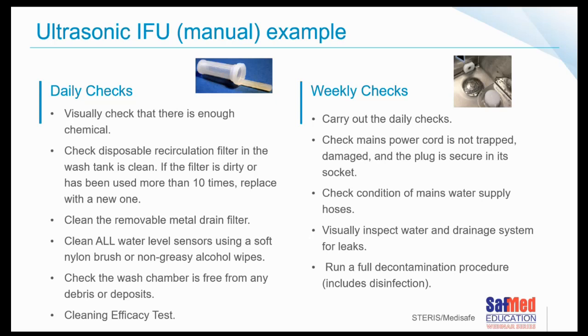A lot of them have got water level sensors, so that's how it knows how much to fill. Of course, it fills up a set amount and doesn't overflow. There's some form of sensor to measure that, and you may need to clean those using a nylon brush or an alcohol wipe, whatever the instructions say. Check that the chamber itself is free from any debris or deposits. You may need to be doing, and you should be doing, cleaning efficacy tests. How often are you doing them? How are you doing them? And then there may be weekly checks, in addition to your daily checks: checking the mains power cord is okay and not trapped or damaged, the plug is secure in its socket, checking the condition of the main water supply hoses, visually inspecting the water and drainage system for leaks, and running a full decontamination procedure that may include disinfection.